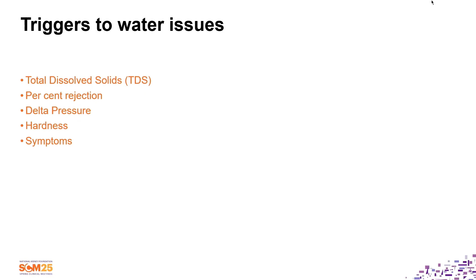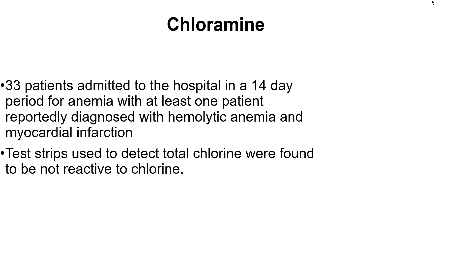Okay. This water issue: 33 patients were admitted to the hospital in a 14-day period for anemia, with at least one patient reportedly diagnosed with hemolytic anemia and myocardial infarctions. The test strips used to detect total chlorine were found to be non-reactive to chlorine. So what we're looking for is a concentration of anything greater than 0.1 part per million. In that scenario, the strips were found not to be reactive, and CMS actually went out into the field to ensure that every facility was performing what on their strips?